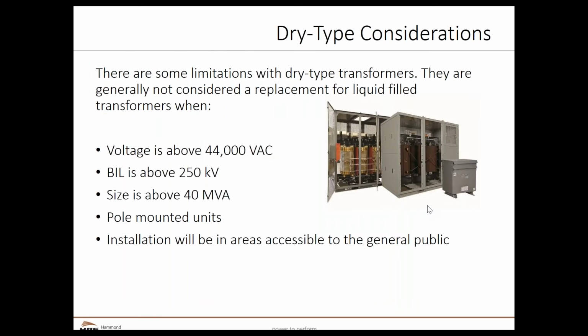So dry type transformers. Right now we're looking at applications below 44 kV. The BIL, which is the basic impulse level, the highest voltage level that transformer can hit by a lightning arc, we're looking at 250,000 volts, 250 kV, for dry type. Typically, dry type transformers will be 40 MVA and below. That's a pretty big transformer. But when we start talking about 100 MVA main power transformers, typically high voltage units, those are really the domain of liquid-filled transformers. Pole-mounted units, we already addressed that earlier in our conversations.